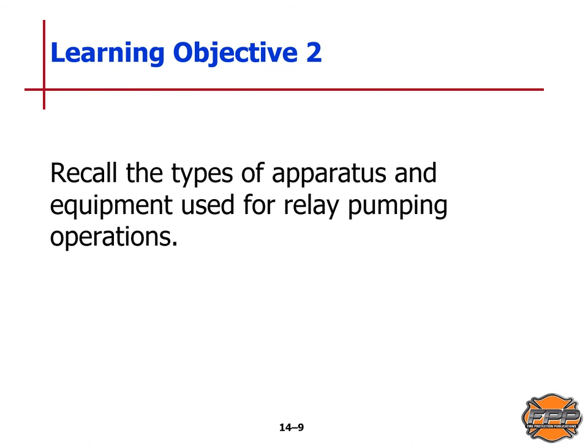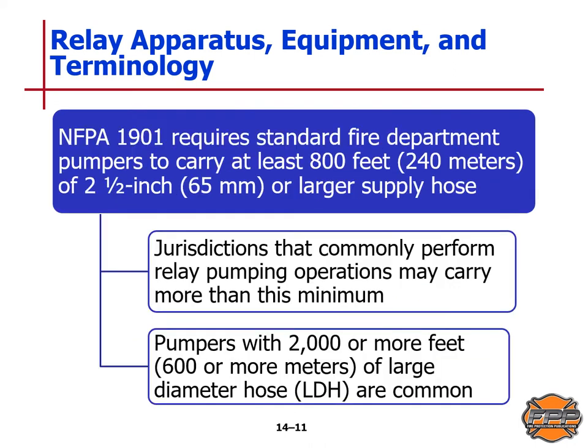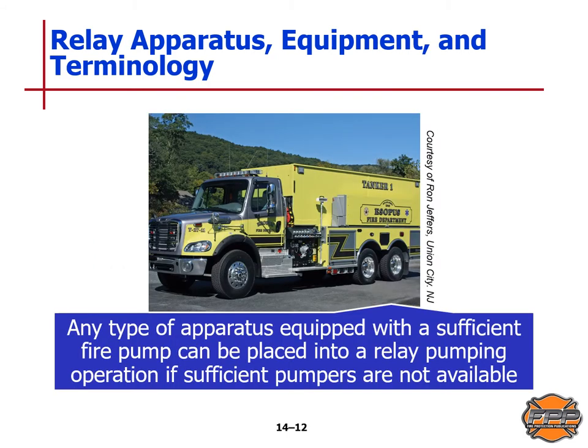Learning Objective 2. In this section, we will recall the different types of apparatus and equipment used for relay pumping operations. A successful relay pumping operation requires various types of apparatus, hose, and equipment. NFPA standard 1901 requires standard fire department pumpers to carry at least 800 feet or 240 meters of two-and-a-half inch or 65 millimeter or larger supply hose. Jurisdictions that commonly perform relay operations may carry more than this minimum. Pumpers with 2,000 or more feet or 600 or more meters of large diameter hose are common. Any type of apparatus equipped with a sufficient fire pump can be placed into a relay pumping operation if sufficient pumpers are not available.